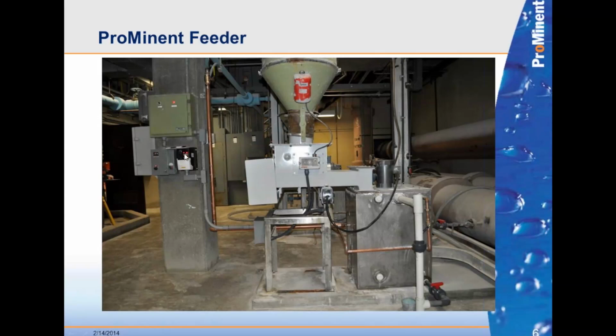The other thing that they have here is on this pillar over here. That is the VFD drive. So now, when the operator comes down, they don't have to worry about any of that. They can come down, there's a little dial in there, and they have a hertz readout on that, normally running about 11 hertz. They can speed it up or down as they need to. It's an instantaneous change. They save the 2 to 3 hours that they were playing around with stuff. And also, it's not hooked up now, but they have the capability of running a 4 to 20 milliamp control to that, tied back to their SCADA up on the second floor, so they could adjust their flow rates without getting off their chairs up there. So it's all built in for that.